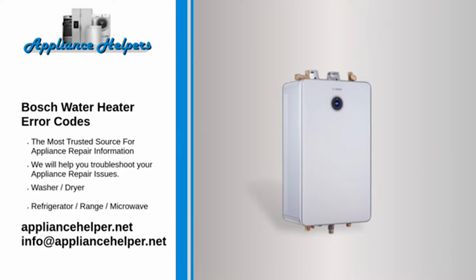Code C7. Problem. Fan rotational speed sensor. Fix. No signal from the fan's rotational speed sensor. The sensor might be broken. Check the wire connection on the control board and fan. The voltage needs to be 120 VAC and adequately grounded. Ensure that the fan and control unit are not damaged.